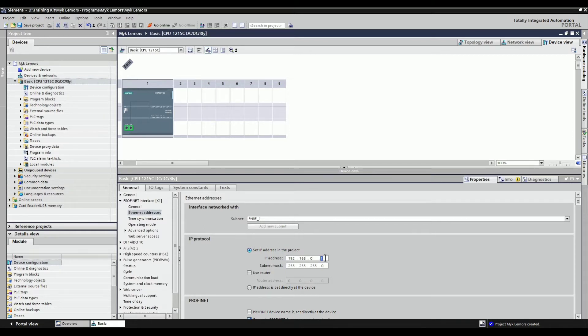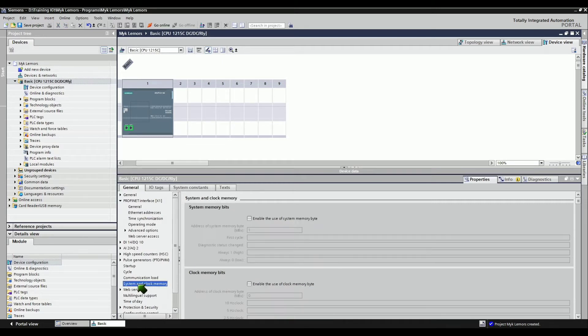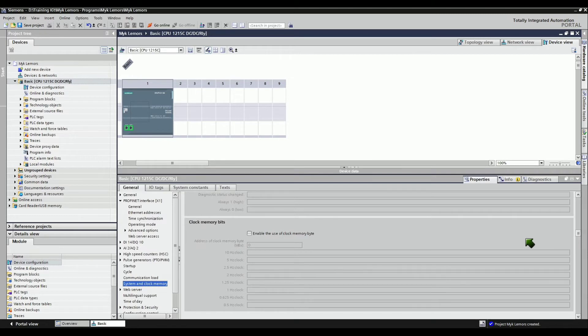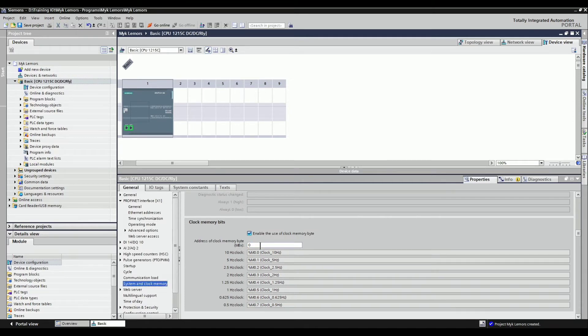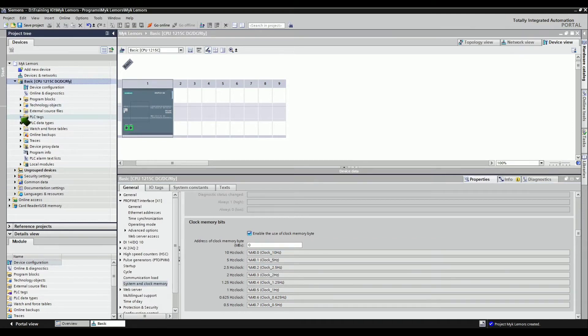Or you can just leave the default value. On the system and clock memory in the Inspector window, click the box to enable the use of clock memory byte for the example project. You can change the address of the clock memory byte or leave the default value. The address of the clock memory byte will automatically be added under the PLC tag of the default tag table.